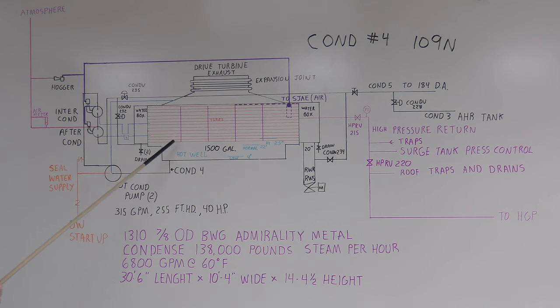This went through a trap and that water went back to the surface condenser. Off your after condenser, the air here went to atmosphere. It had an air meter so you could check for air in-leakage. So this is one way to pull vacuum on a surface condenser - another way is with liquid ring vacuum pumps, but this system worked really quite well.